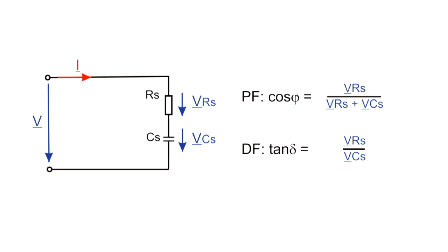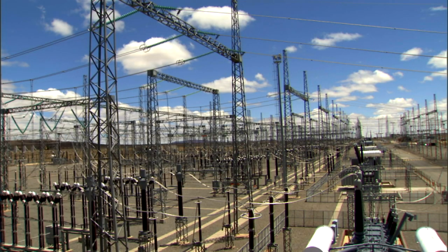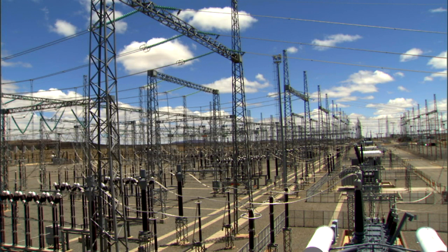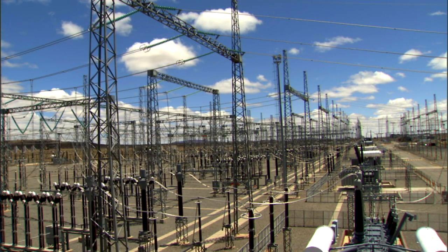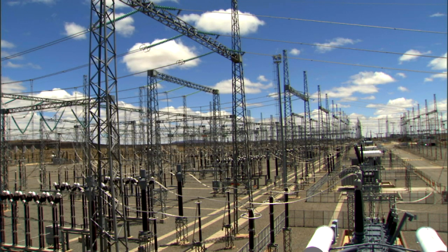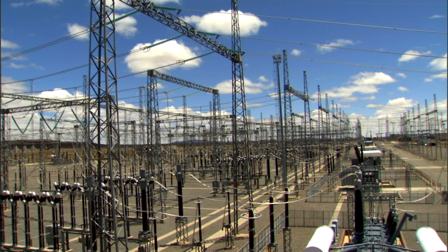In principle, the power factor or the dissipation factor at power system frequency can be represented with a parallel or a series equivalent circuit. To get a better understanding of both types of losses, it is advantageous to measure the dissipation factor or the power factor over a broad frequency range.